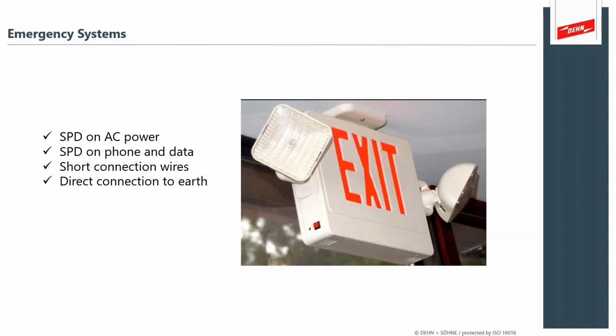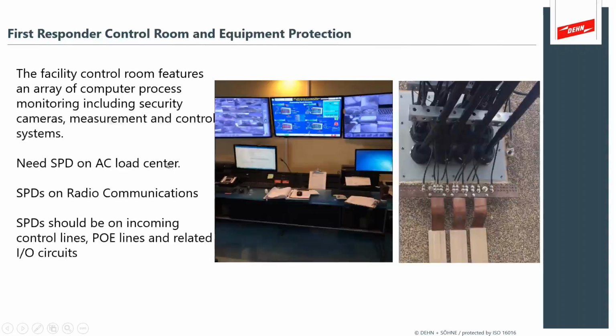So this is a clear, easy place to make sure that is taken care of first, and the same applications apply for the product near the point of use, with a short connection and direct connection to earth. So control rooms at first responders, control rooms in your IO factories, in your process industry, wastewater, power generation. Everybody has something that looks probably similar, where you've got the SPDs at your load center.